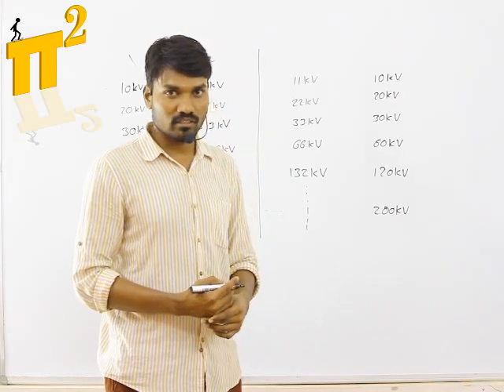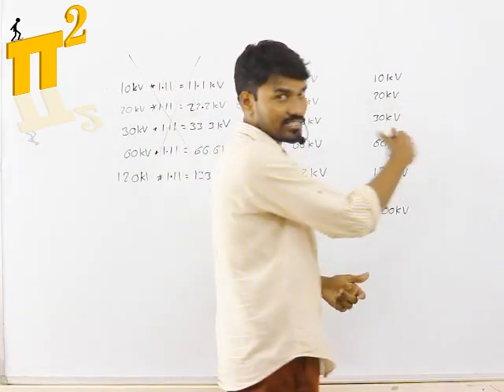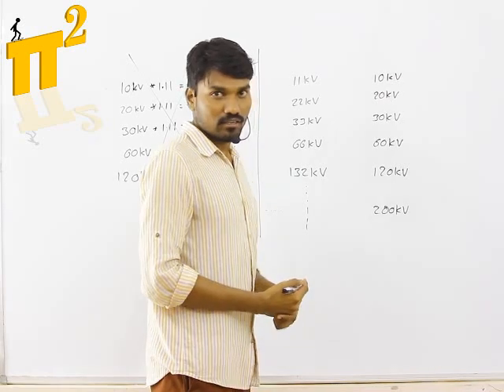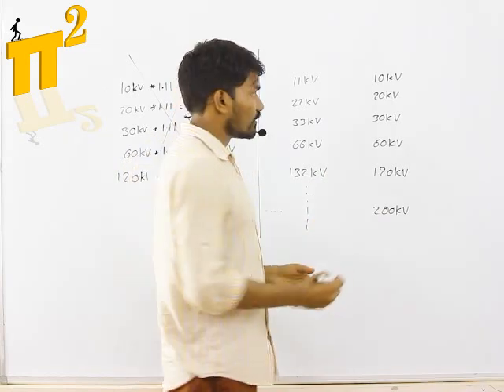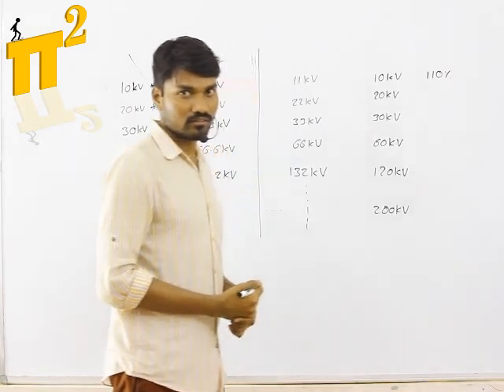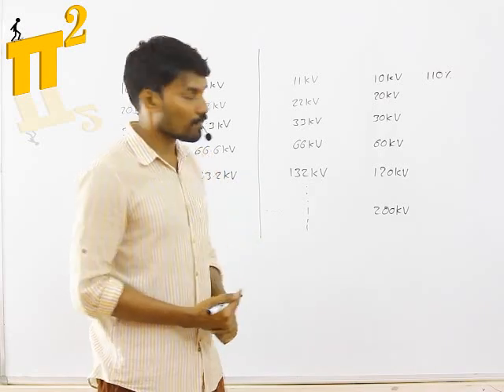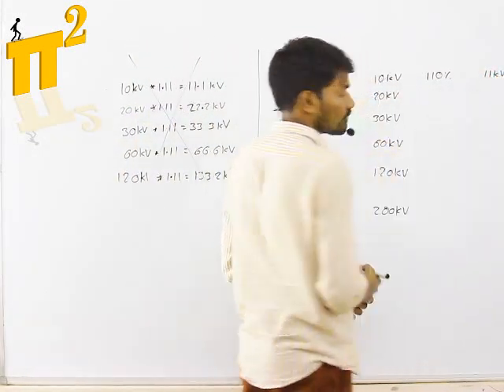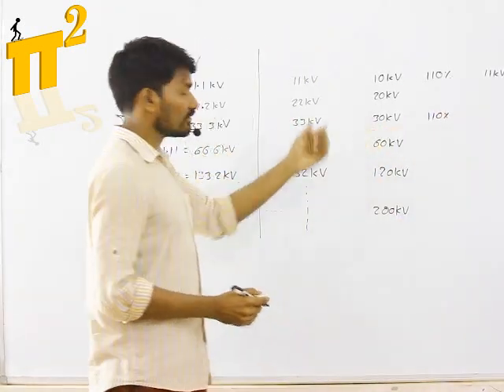But they know that in the transmission process there is a voltage drop, because of transmission line resistance. So they transmit 10 percent extra. They intend to deliver 10 kV at the receiving end, but at the sending end they transmit 110 percent of 10 kV — that is 11 kV. Likewise, 110 percent of 30 kV is 33 kV.